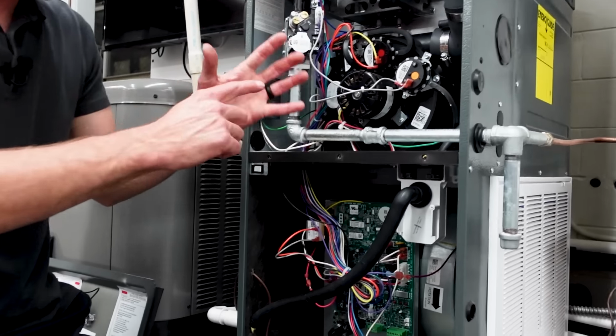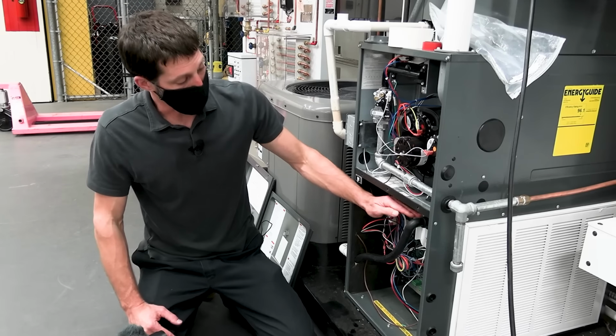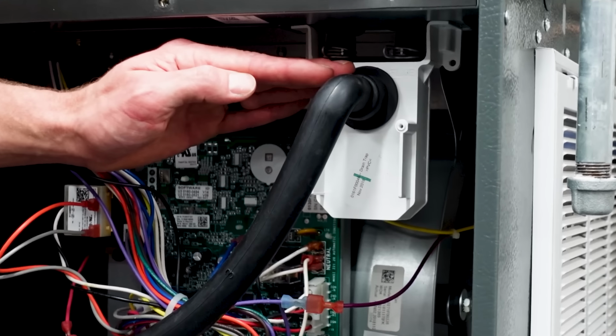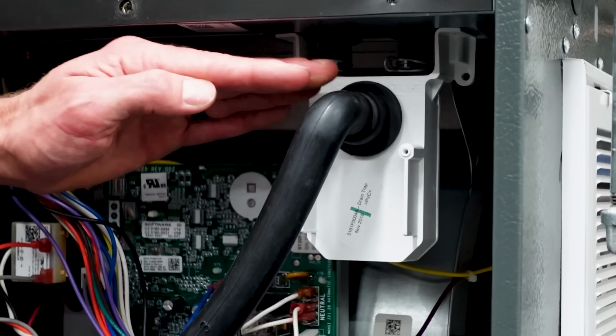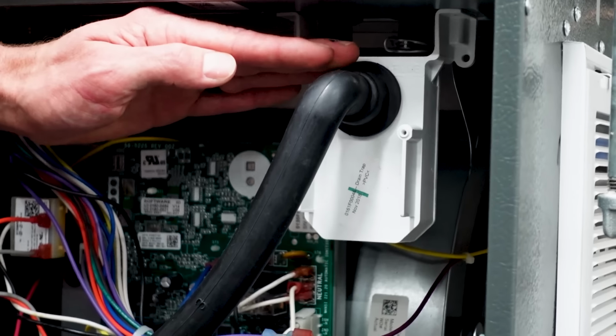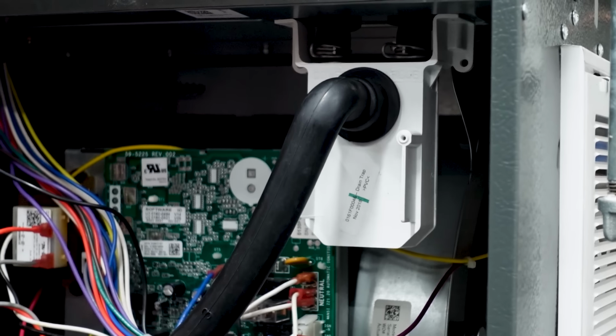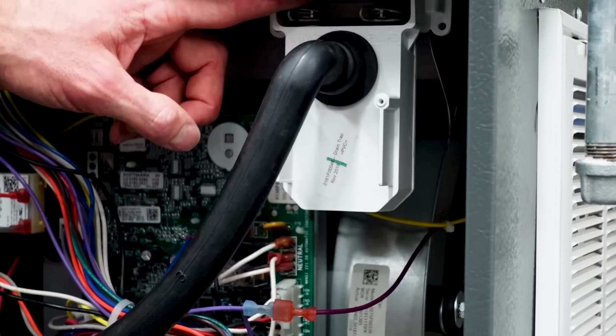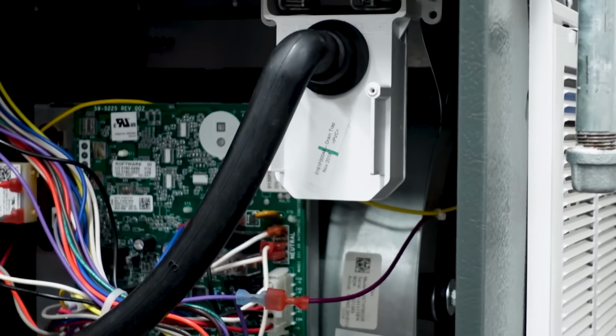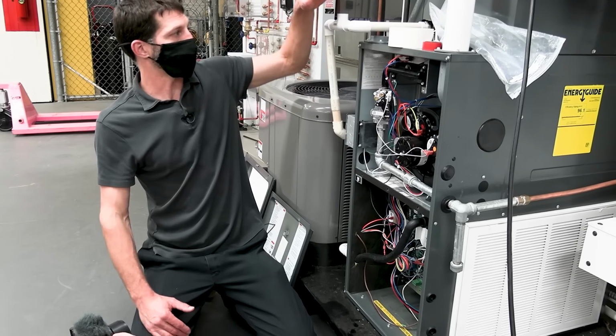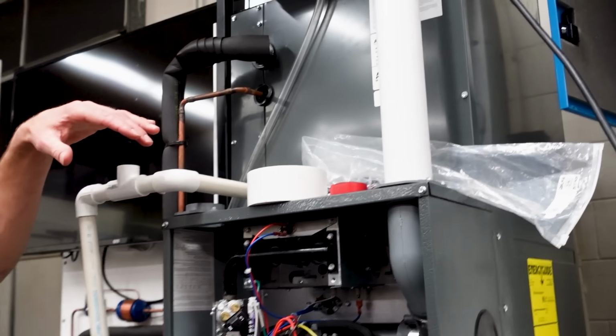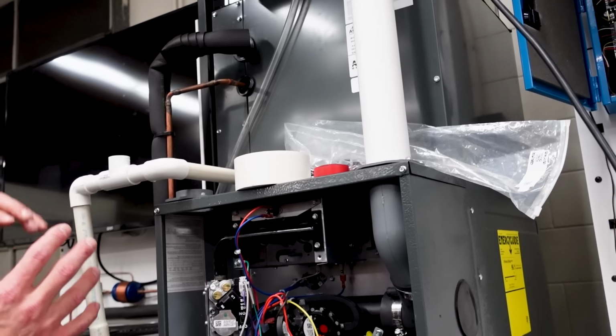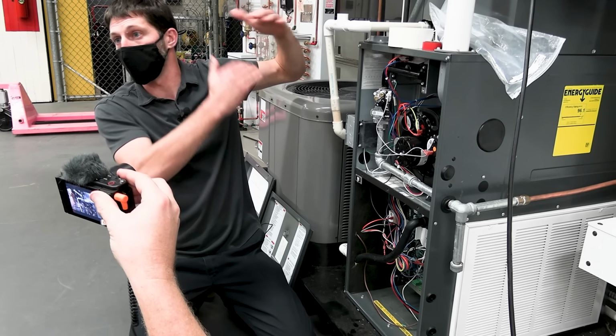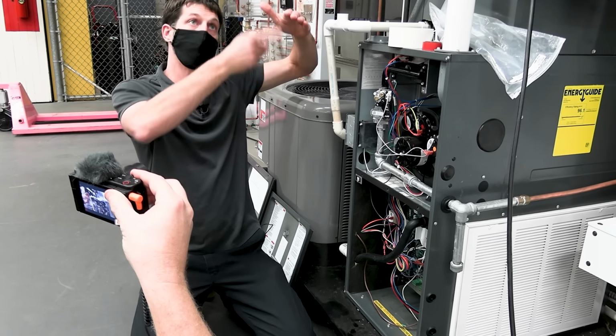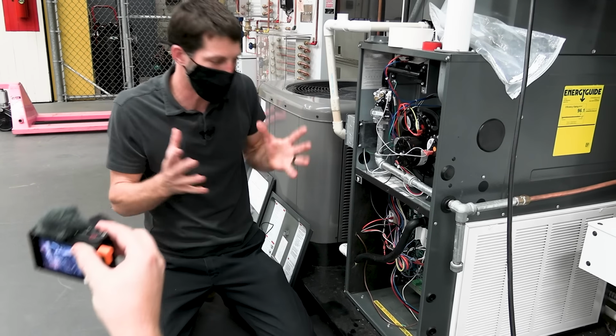It's all molded and it's got chambers in there, but the reason for the trap is the water height level. The weight of the water is able to allow the condensate to travel out of here, even though right above it is negative pressure from your inducer motor. So it's kind of the same premise as a trap on an air handler for air conditioning mode. The water weight is what allows the condensate to flow down the tubing. It's kind of the same principle.